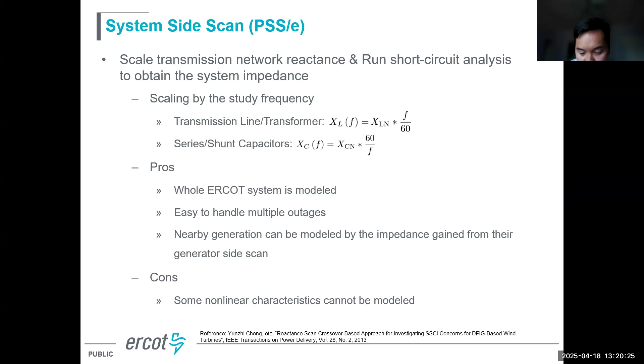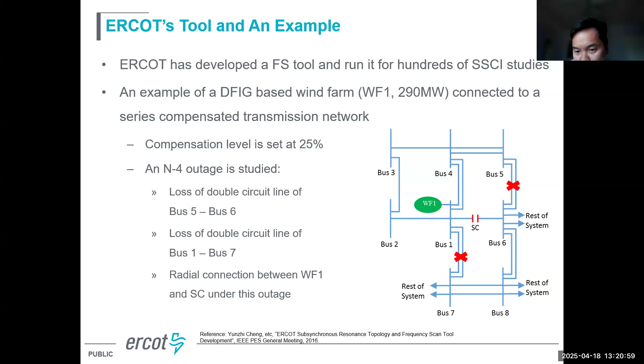So an example here is, you have wind farm 1, and if we trip the double circuit between bus 5 and bus 6, and then the double circuit from bus 1 to bus 7, then this wind farm will be radially connected to the series compensation. Then we run a frequency scan under this condition. This is the wind farm impedance, and this is the system side impedance under the N-4 contingency. And then, as I said, we add them together.